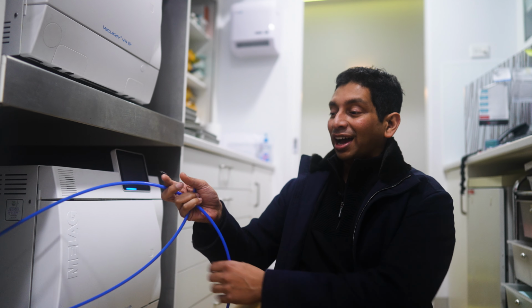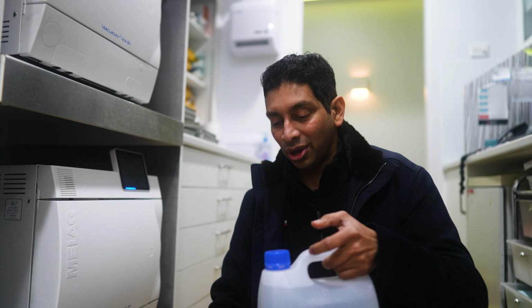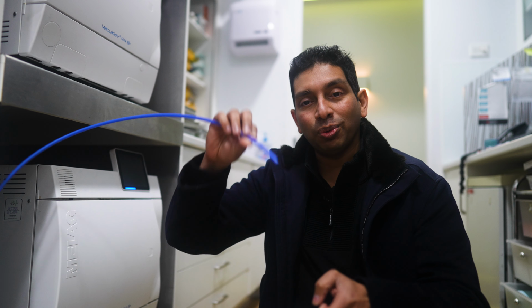These autoclaves don't have an internal water reservoir because they take everything straight from the plumbed-in pipes. And these are the pipes. Now, again, for redundancy, what I've done is I got the plumber to plumb them in so we can use an external tank if we wanted to. So if there's anything that happens to the reverse osmosis unit or something with the water, we can actually open this, put this in there, and it'll suck up the water from these tubes. Now that sounds great in theory, but in order to make that happen, there's 2 valves on each autoclave that you need to change, and then you get confused. And if you get confused, water actually leaks out of this, which isn't ideal. So that can be a potential issue. So I'm the only one that's allowed to switch those across.